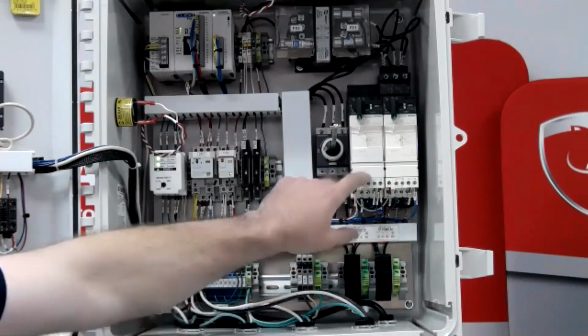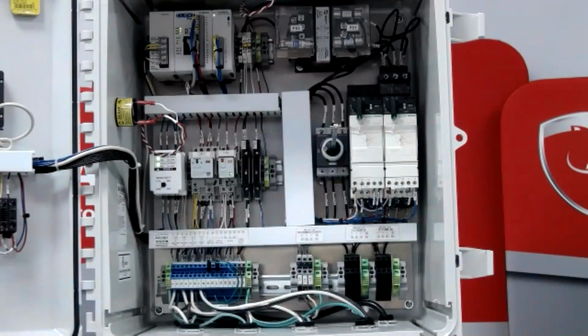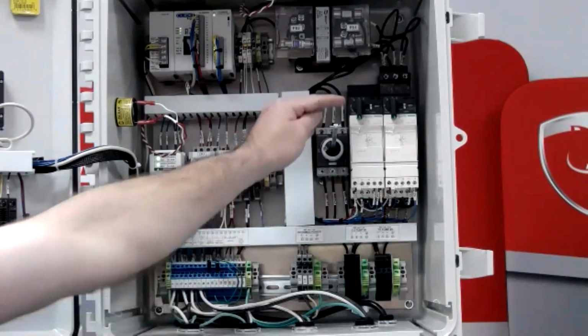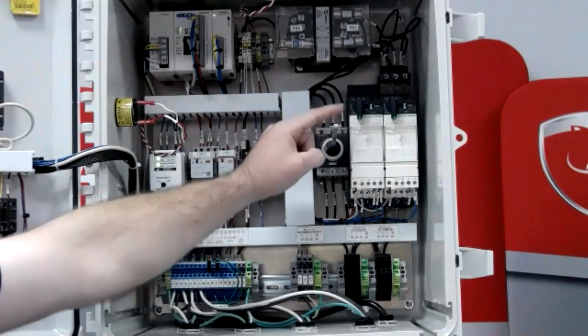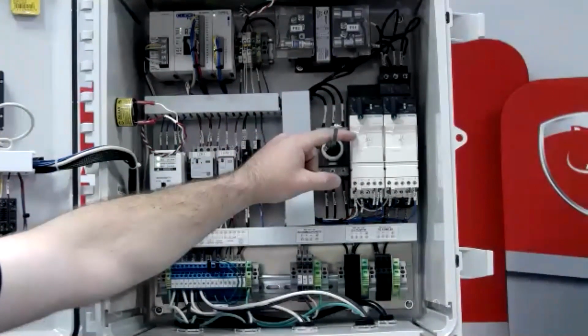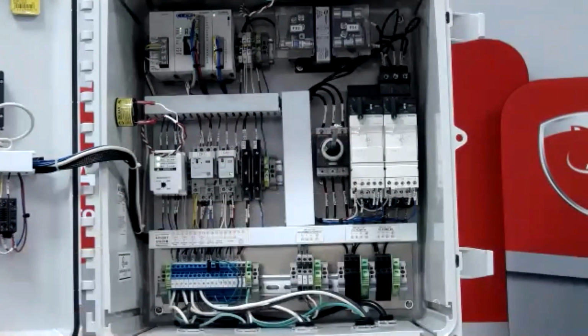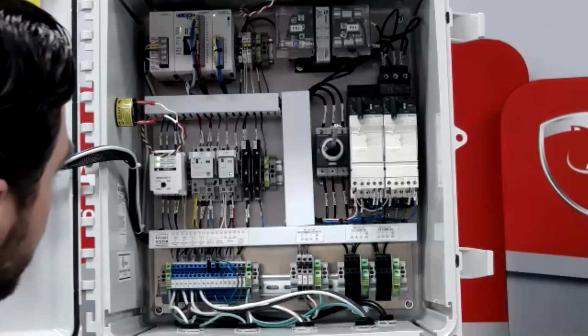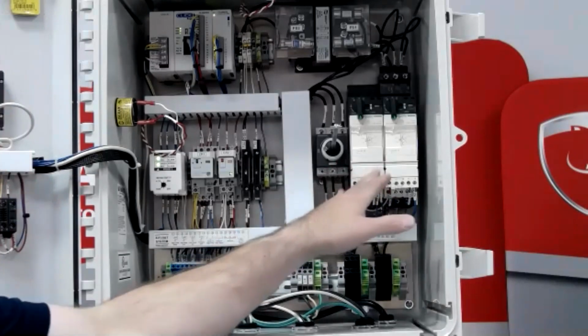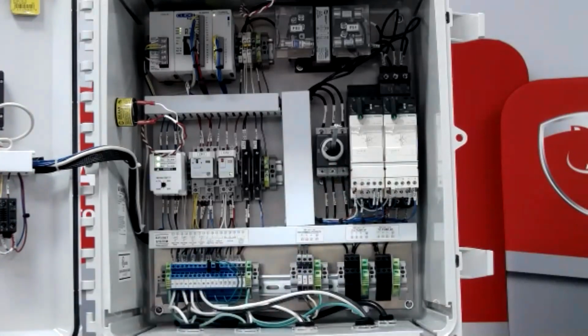And we're using a little bit different style of combination motor starter there that gives us our circuit breaker with the lockout tagout. It's giving us the overload protection for the motor as well as the contactor in one compact unit. You got a little bit wider range of overload ratings there.